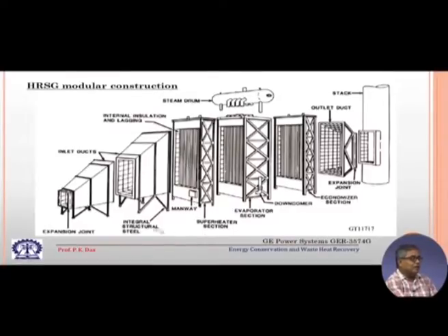First one is the superheater, we can correlate with our earlier diagram. So, this is the superheater section. Then we have the evaporator section. In the evaporator section, at the top there will be the boiler drum. So, this is the boiler drum and these are the many tubes, and on the backside also there are tubes. These are basically risers; there will be a large number of risers through which steam water mixture will come to the steam drum and get separated.